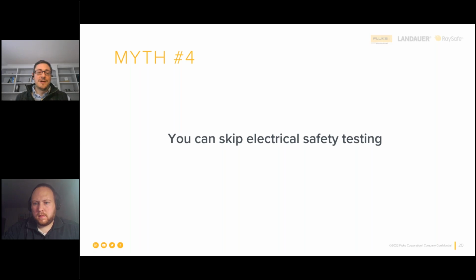Elliot, any other examples you might want to throw out there? Yeah, even with initial inspections of equipment coming into the OR for cases being done with local OEM reps, it's important to go and do electrical safety on that equipment. Just because maybe they grabbed a power cord they found in a bin somewhere in the hospital, and that cord was supposed to be thrown out — the reason being that electrical safety testing had determined that power cord was making the product fail basic electrical safety. Power cords in general, or devices in the hospital, sometimes get corroded, old, bent, or cut open, and they need to be checked and rectified as soon as possible.